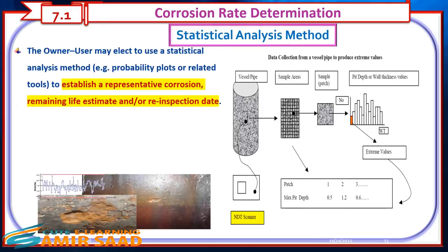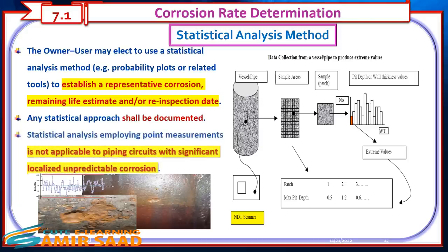Statistical Analysis Method: The owner or user may elect to use a statistical analysis method — for example, probability plots or related tools — to establish a representative corrosion rate, remaining life estimate, and/or re-inspection date. Any statistical approach shall be documented. Statistical analysis employing point measurements is not applicable to piping circuits with significant localized unpredictable corrosion.